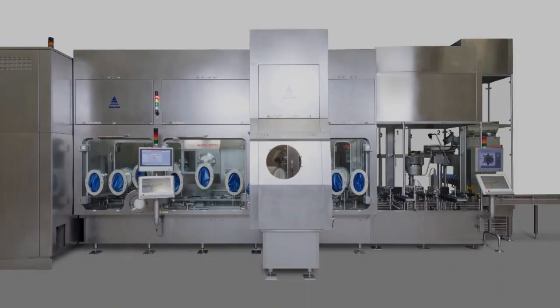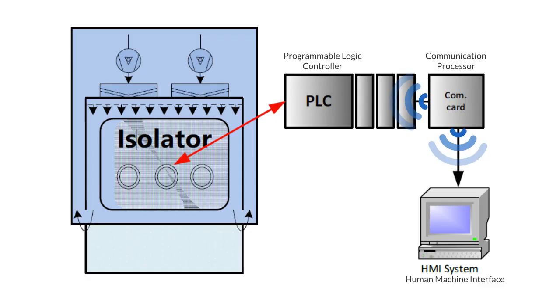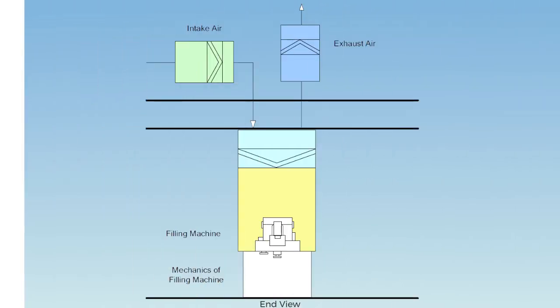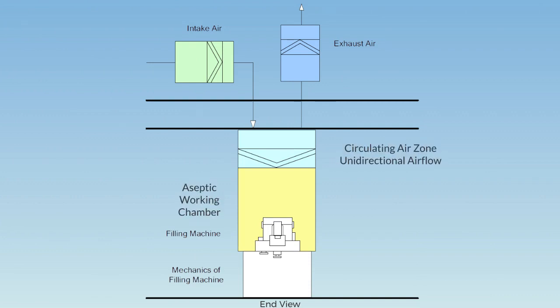The Line 2 isolator is a rigid wall isolator made from stainless steel for the enclosure with laminated safety glass for viewing windows. The control system of the isolator is via the Programmable Logic Controller or PLC that includes the Human Machine Interface or HMI. The Line 2 isolator has an aseptic working chamber, a circulating air zone to create unidirectional or laminar airflow, and an air management system, or HVAC, in the technical area.